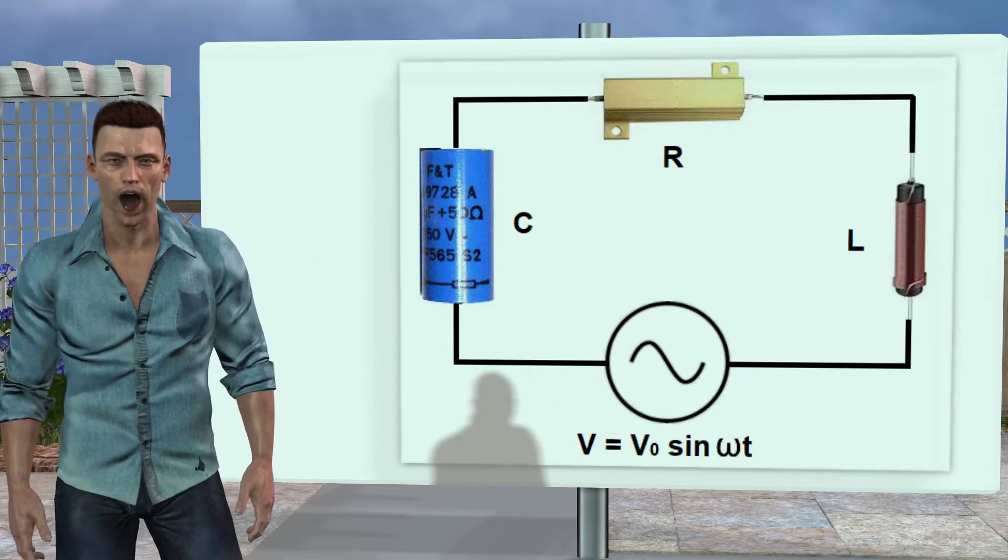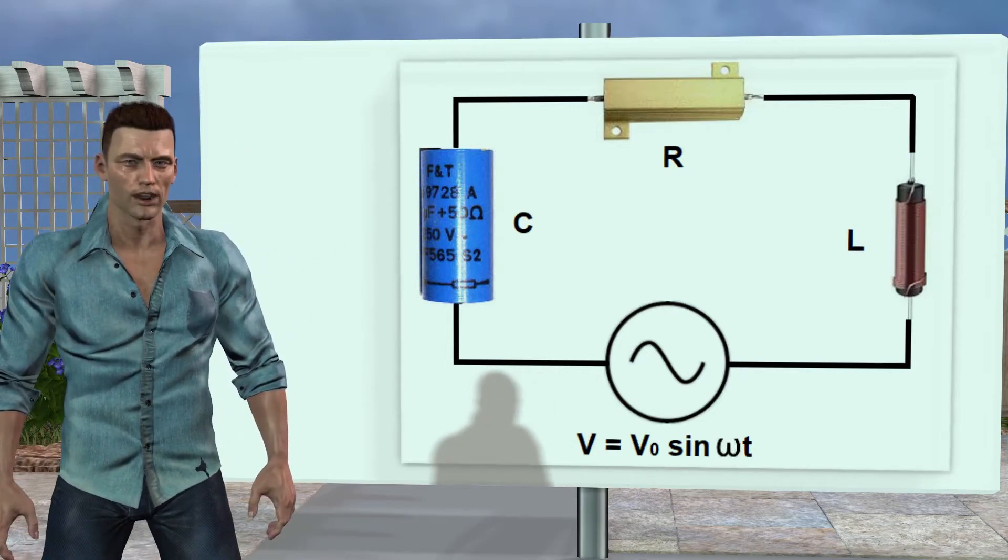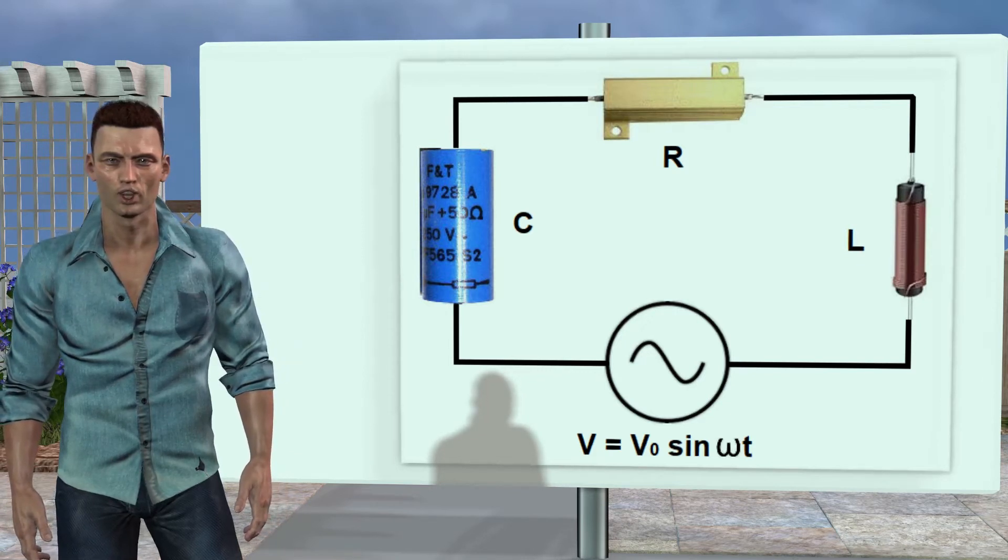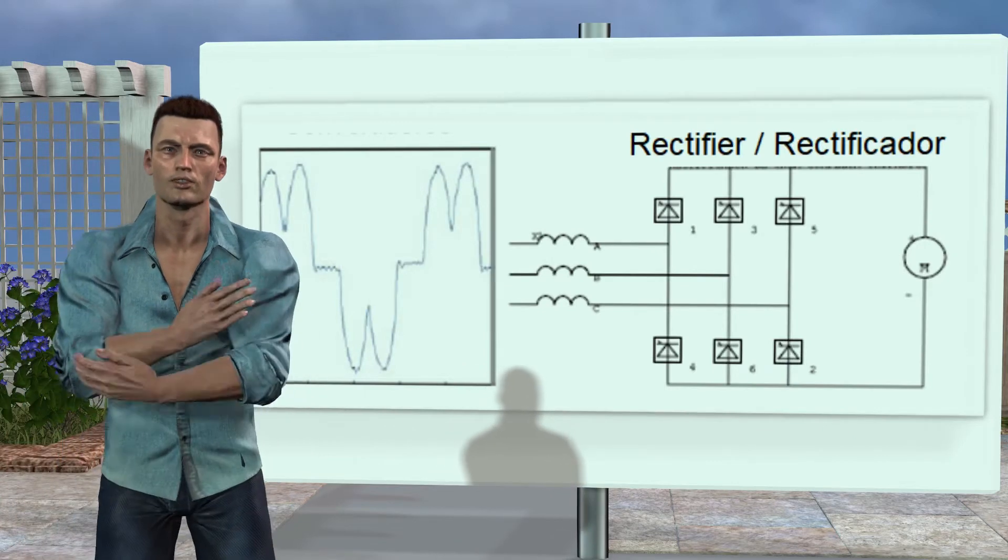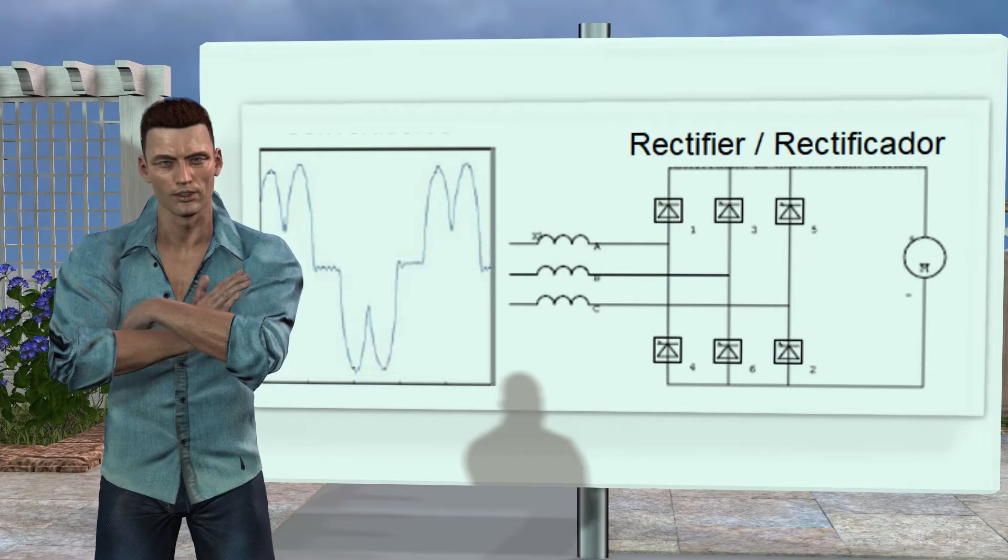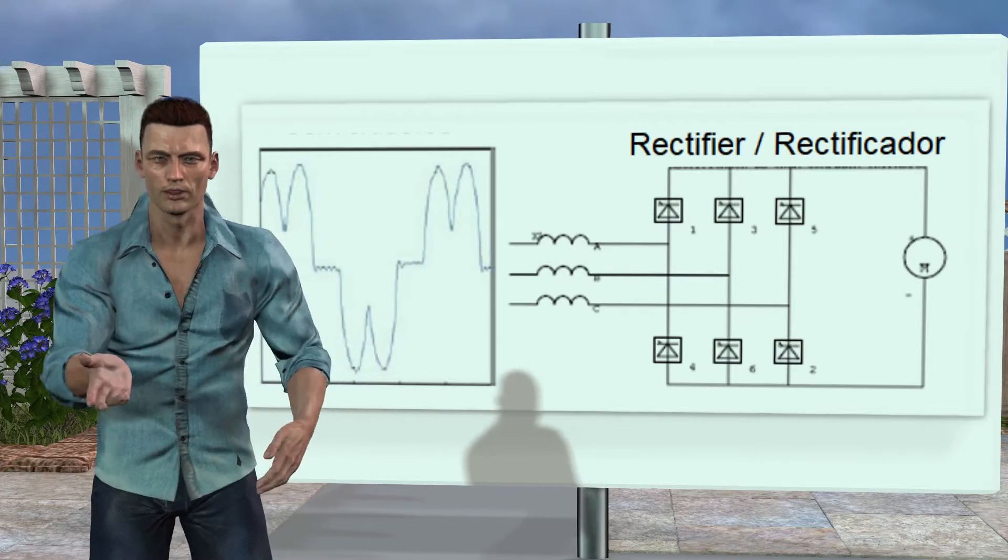For this type of loads, if the voltage is sinusoidal, the currents are also sinusoidal. This is what defines a linear load versus nonlinear loads, in which the current will not be sinusoidal, as it happens with electronic loads like frequency converters, rectifiers, etc.